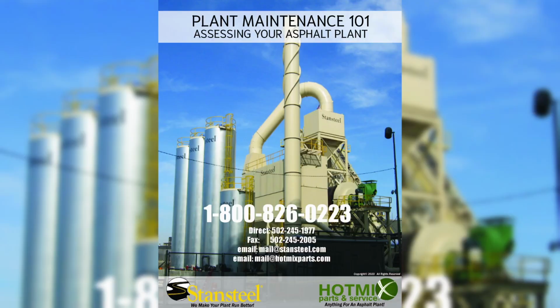We're gonna delve into that, because that's one of my favorite things to bring up to people. If I'm at a plant site and people aren't doing the production they should, or there are nonsensical things potentially going on that don't initially add up, one of the very first places I go is drilling a hole in prior to the fan. And we'll take negative pressure readings. So we're going to get into that. We'll actually be showing you some visuals here overlapping in a little while, where we provide a data sheet.